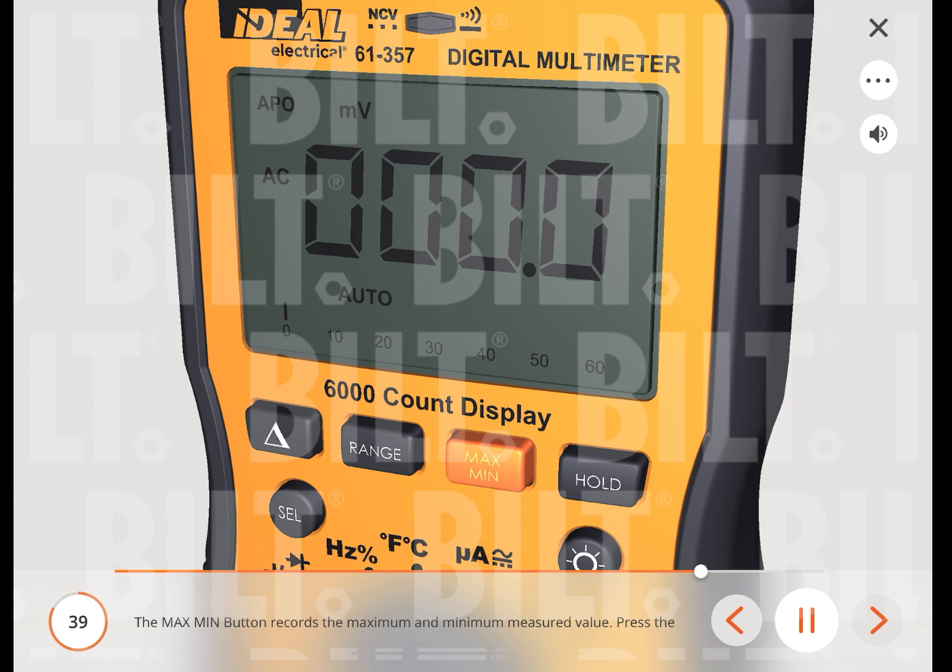The max-min button records the maximum and minimum measured value. Press the max-min button to activate this feature and to toggle between max and minimum readings. The unit will continually capture max and min values over time. Depressing the max-min button for over 2 seconds exits the max-min mode. If the meter is turned off, all max-min data will be lost. Note: when the max-min function is activated, the auto-power-off (APO) feature will be disabled; when you exit the max-min function, the auto-power-off feature is re-enabled.